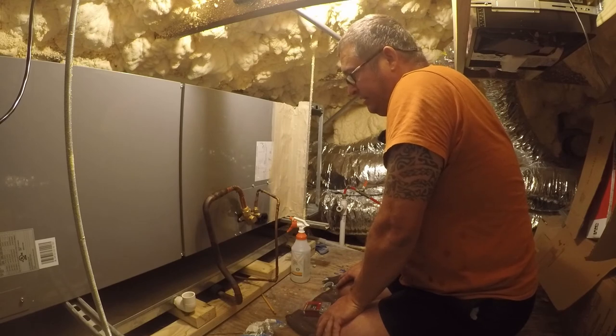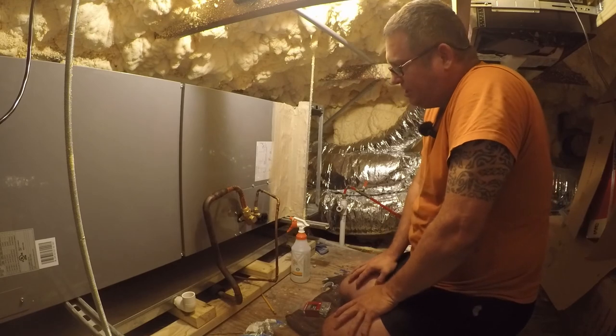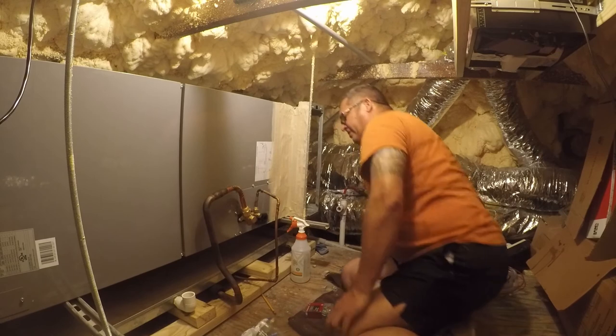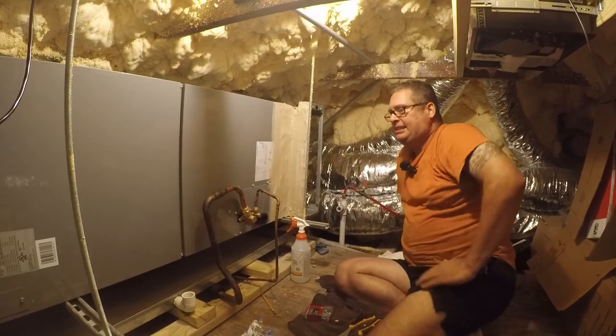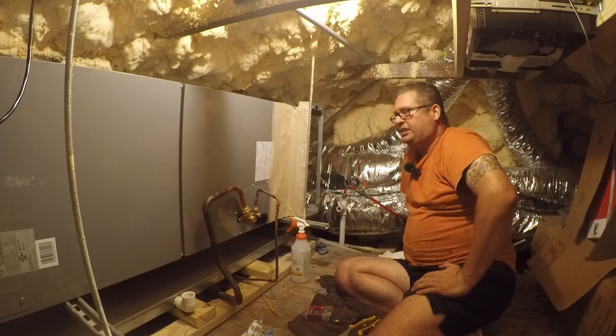And fascinatingly enough, there's service valves up here, which is just bizarre. I wouldn't expect to see mini split service valves on the air handler. My guess is this is just a cost saving measure.